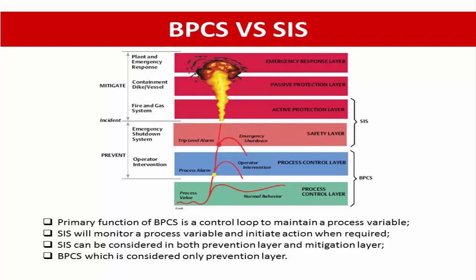This picture shows the SIS, BPCS, and other layers of protection. You can see it accurately presents the difference between BPCS and SIS. The first and second layers are under control within the BPCS — for example, the process control system itself and operator control. Automatic actions triggered by process variables, such as the Emergency Shutdown system, or ESD, or Fire and Gas system, are considered as the Safety Instrumented System. We can notice the SIS can be considered in both the prevention layer and mitigation layer, whereas the BPCS is considered only in the prevention layer, not the mitigation layer.